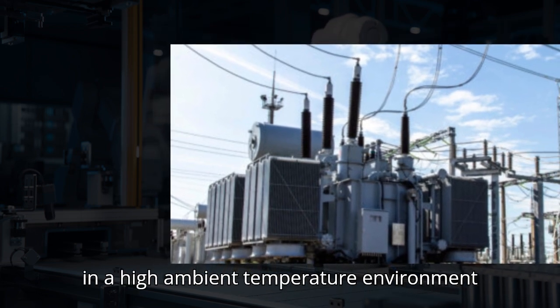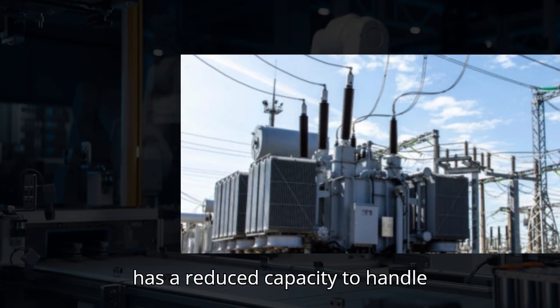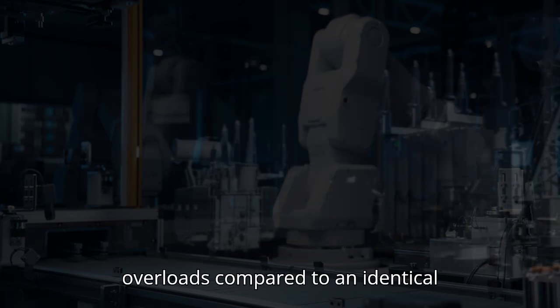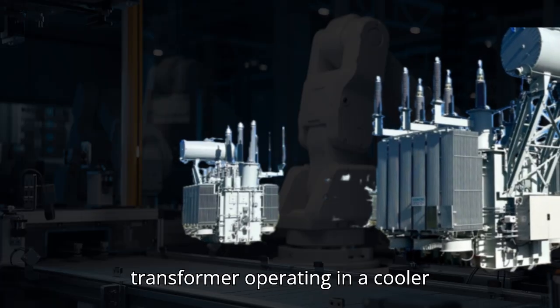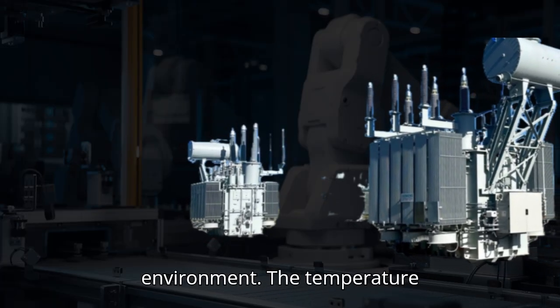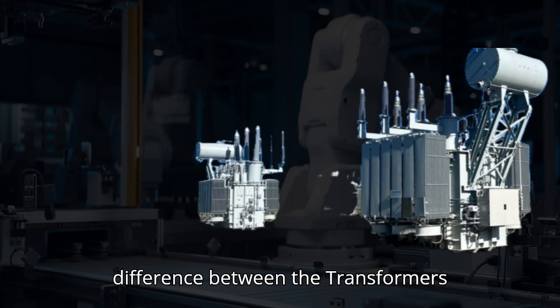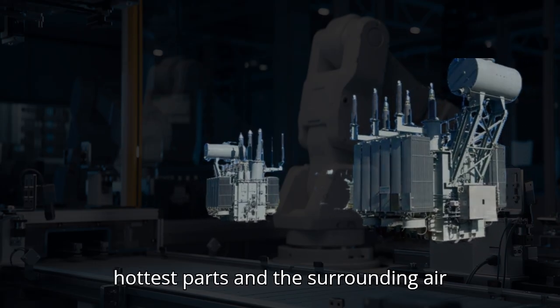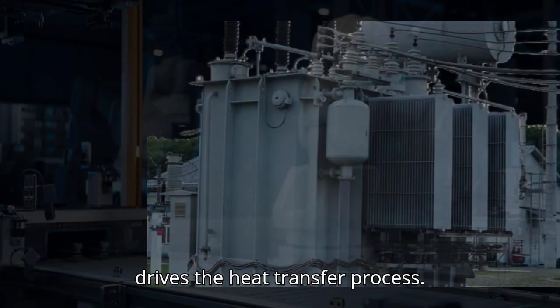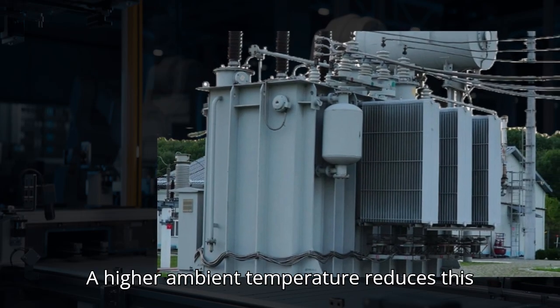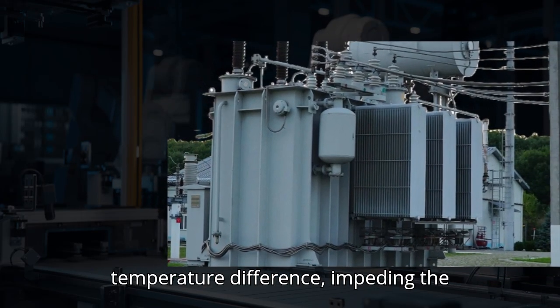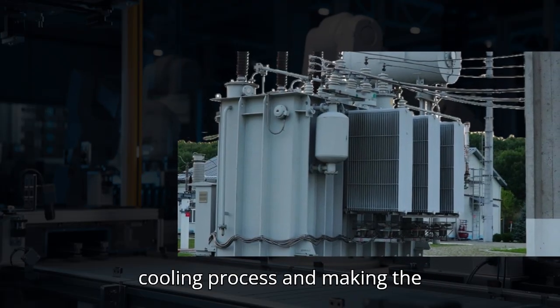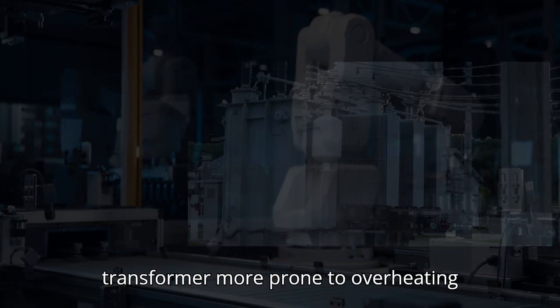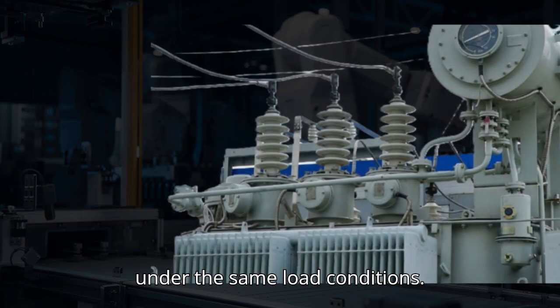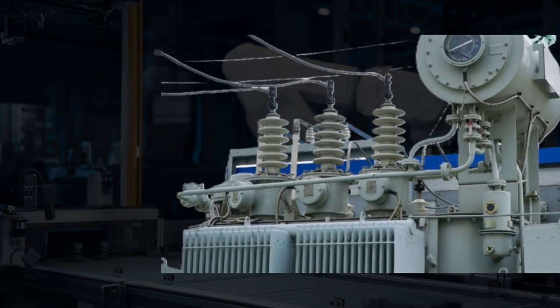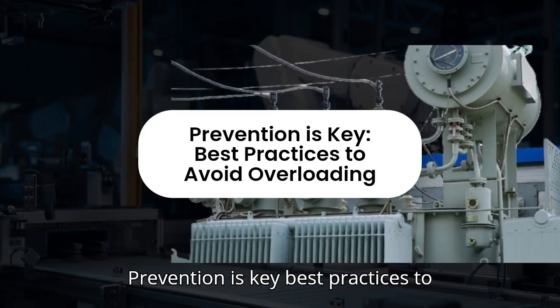A transformer operating in a high ambient temperature environment has a reduced capacity to handle overloads compared to an identical transformer operating in a cooler environment. The temperature difference between the transformer's hottest parts and the surrounding air drives the heat transfer process. A higher ambient temperature reduces this temperature difference, impeding the cooling process and making the transformer more prone to overheating under the same load conditions.